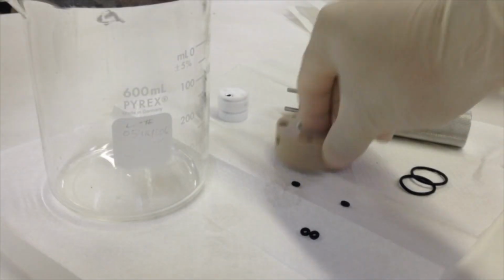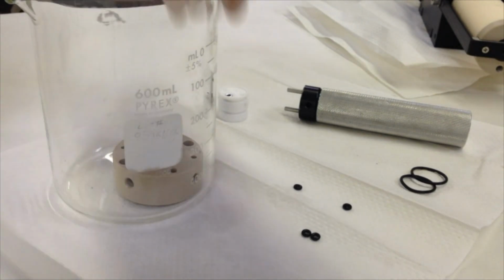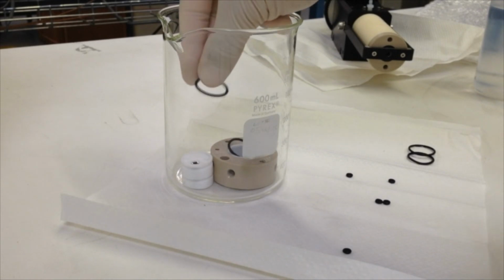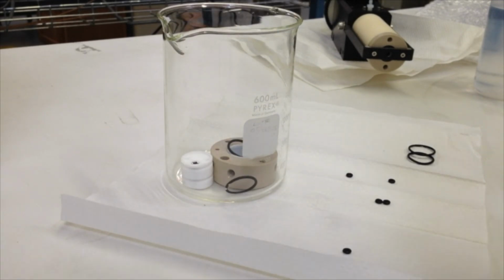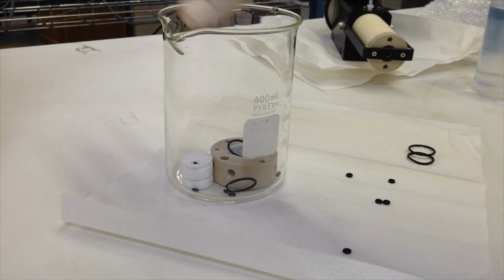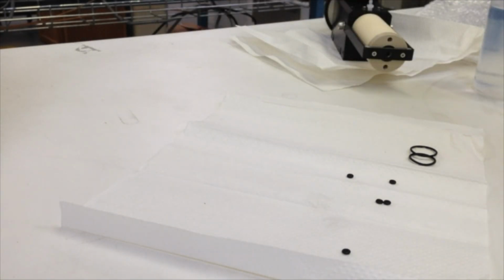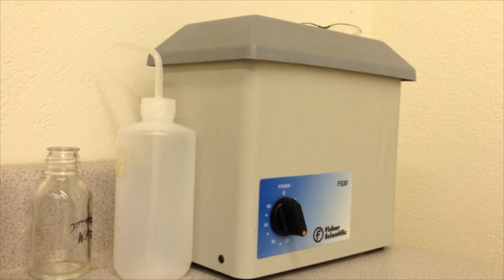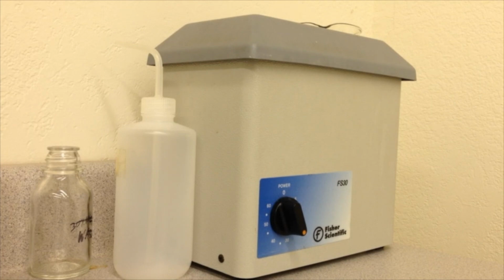Place the valve face and insert along with a set of new valve seals into a clean beaker. Fill with warm water and a few drops of liquid dish soap. Place in an ultrasonicating bath for at least 30 minutes. Afterwards, thoroughly rinse all sonicated parts with DI water. Dispose and never reuse old valve O-rings. You can now install the pumps while the valve components are being sonicated.